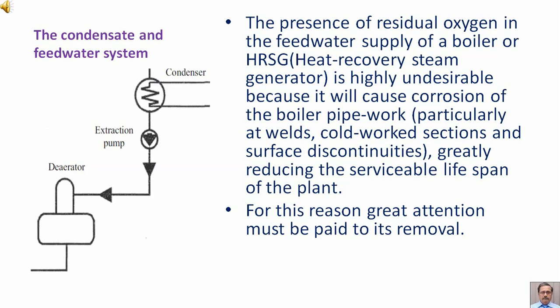The presence of residual oxygen in the feed water supply of a boiler or HRSG (heat recovery steam generator) is highly undesirable because it will cause corrosion of the boiler pipework, particularly at welds, cold-worked sections, and surface discontinuities, greatly reducing the serviceable life span of the plant. For this reason, great attention must be paid to its removal.